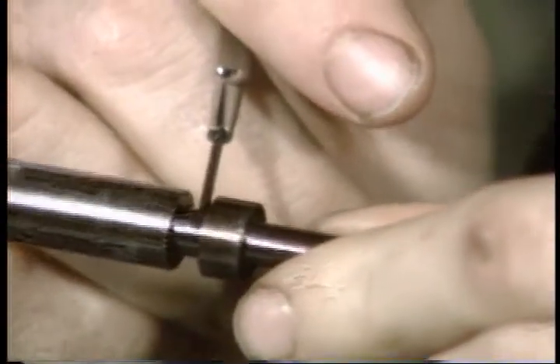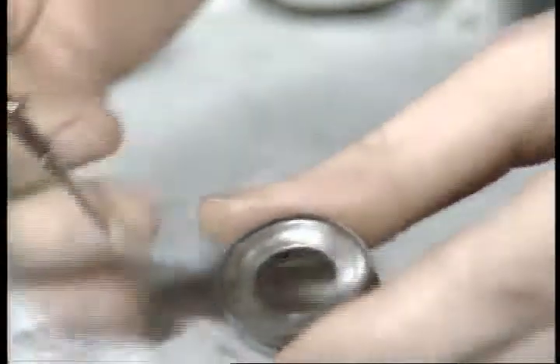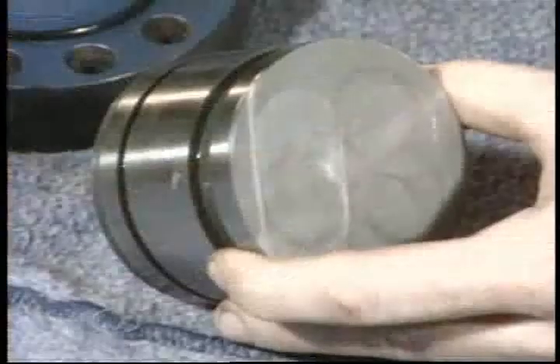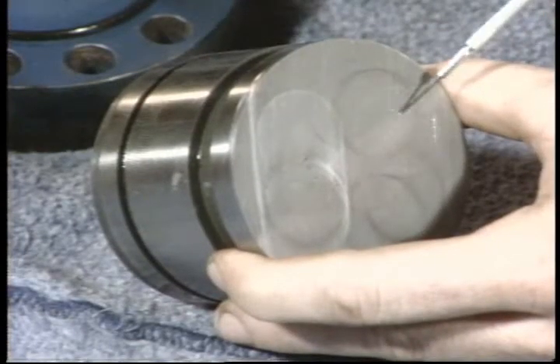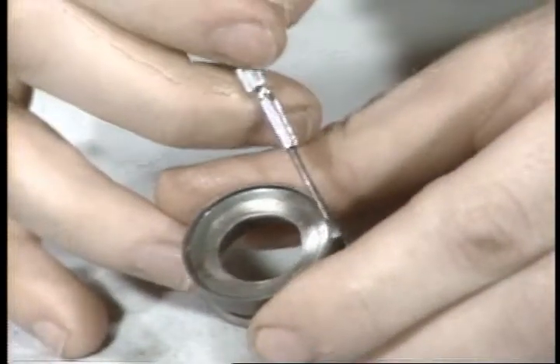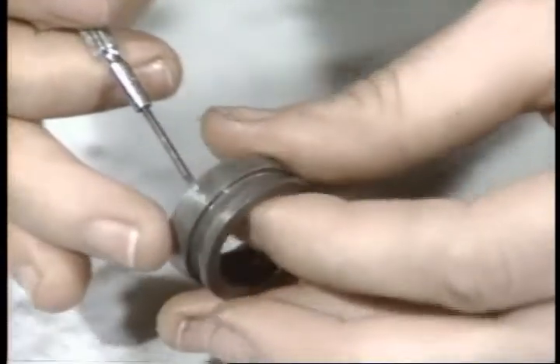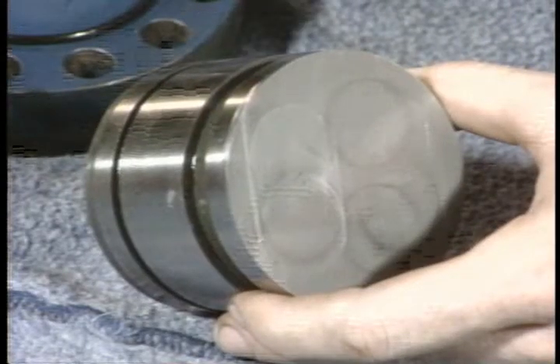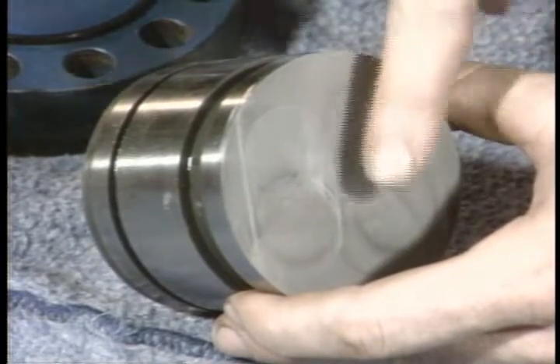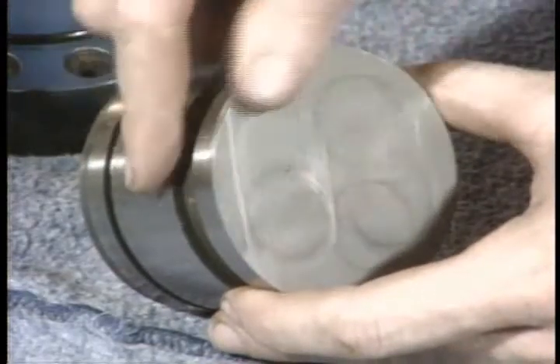All internal metal parts come in the repair kit. In particular, let's look at the seal rings. Inspect the outside edges of the seal rings. They seal against the seal plate and around the inlet port. If they're damaged, any nicks, uneven surfaces, or scoring, replace them. Fluid is leaking over them. And if you have to replace the seal rings, replace the flow and seal plates also.